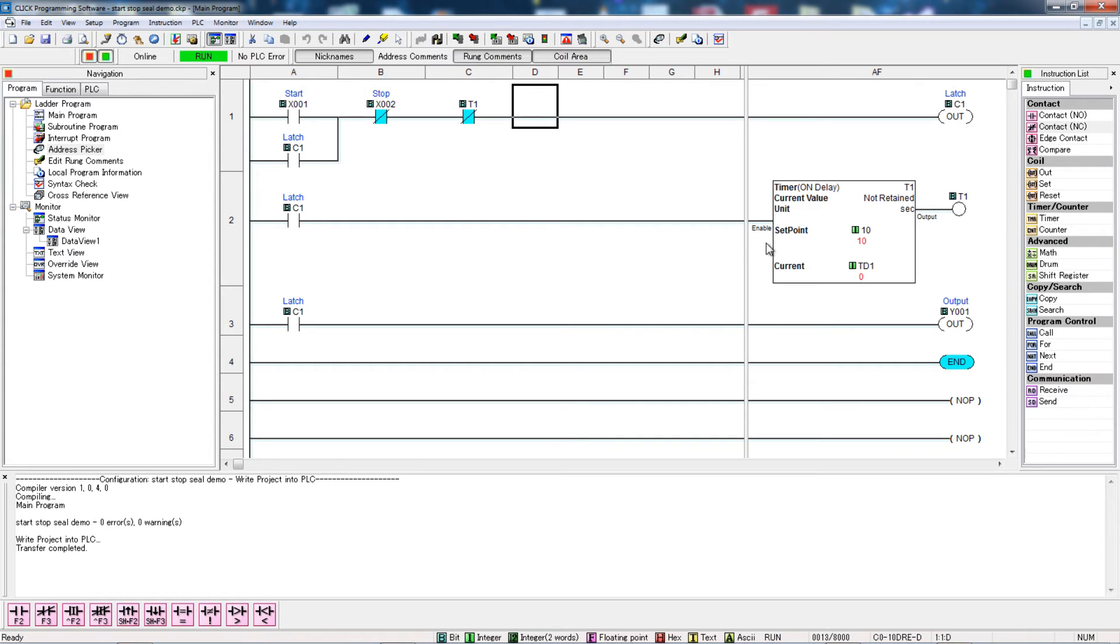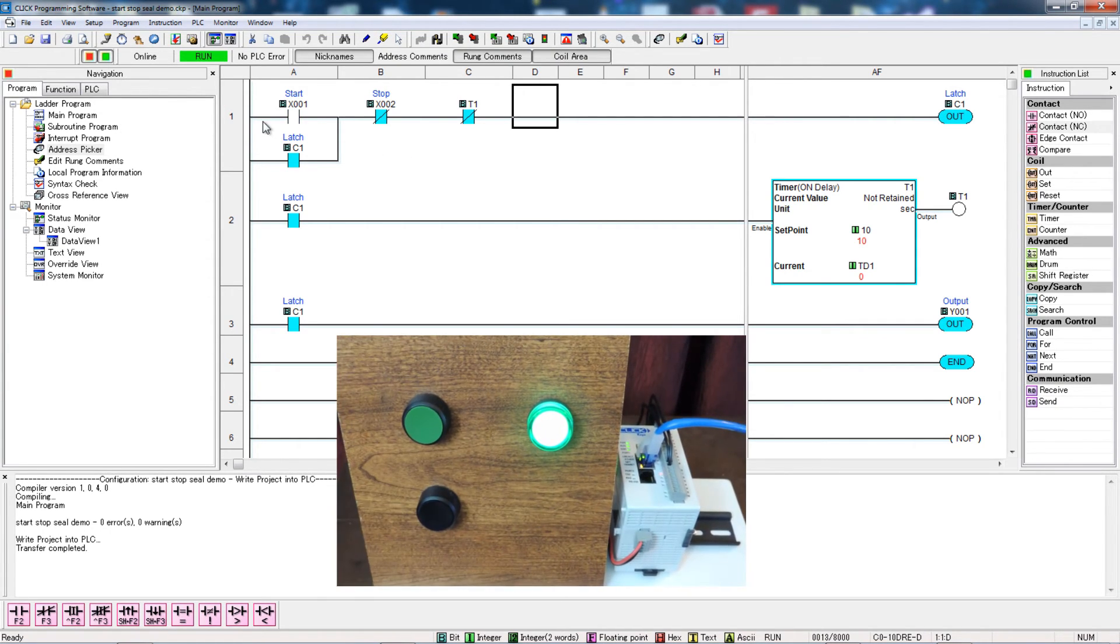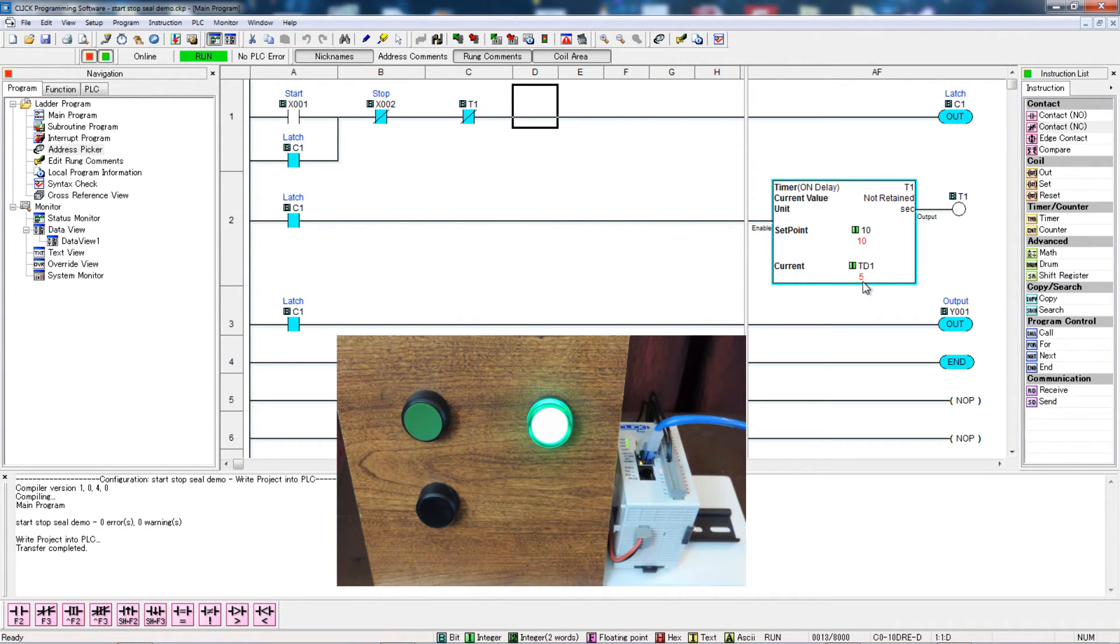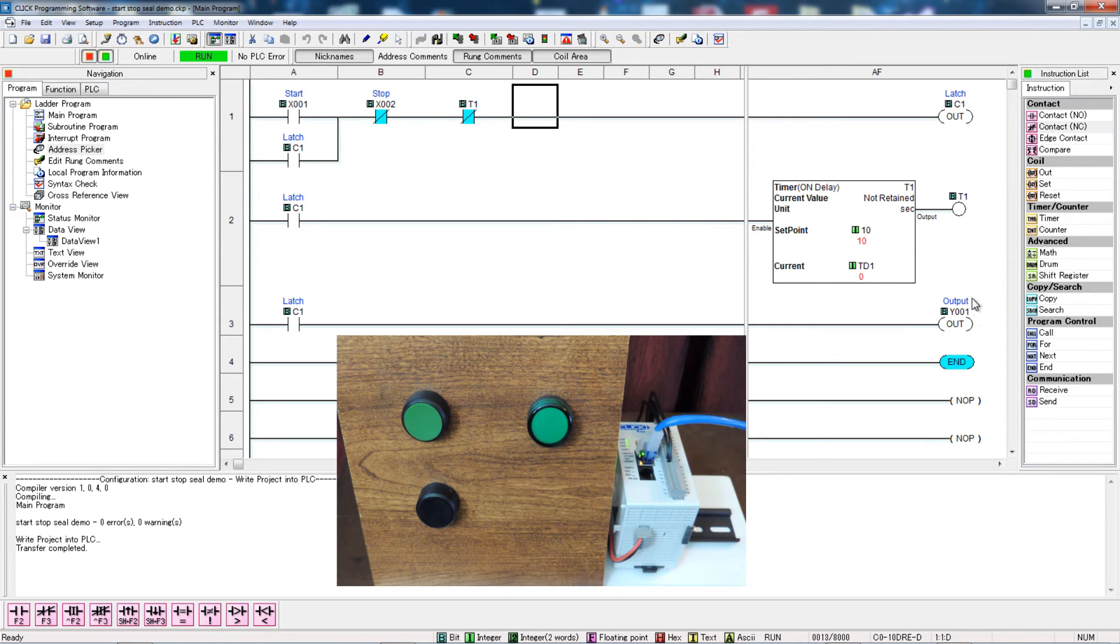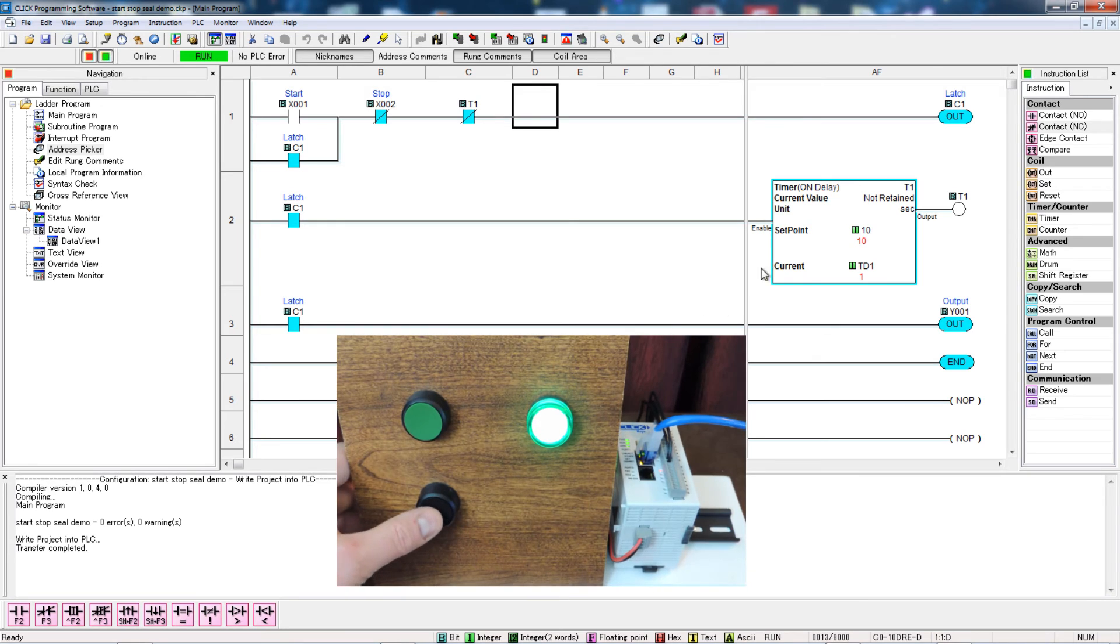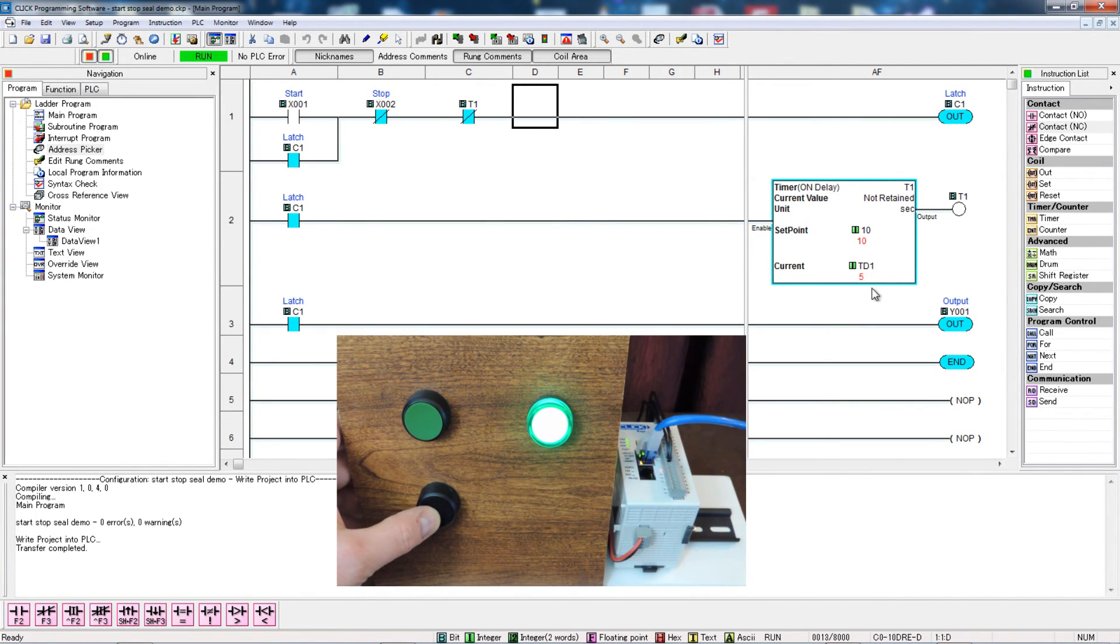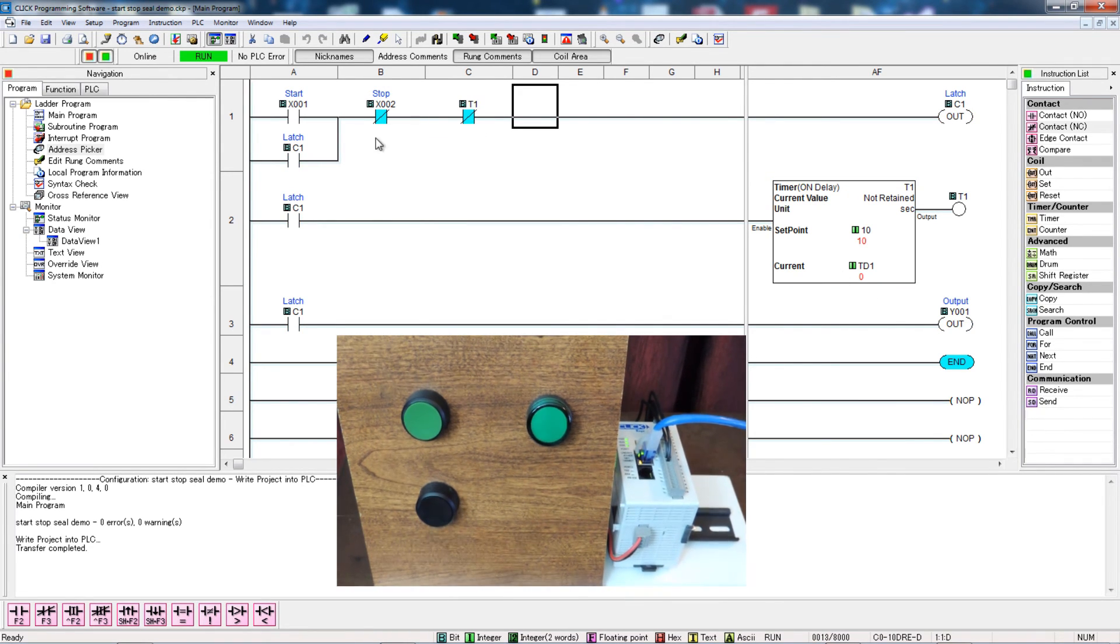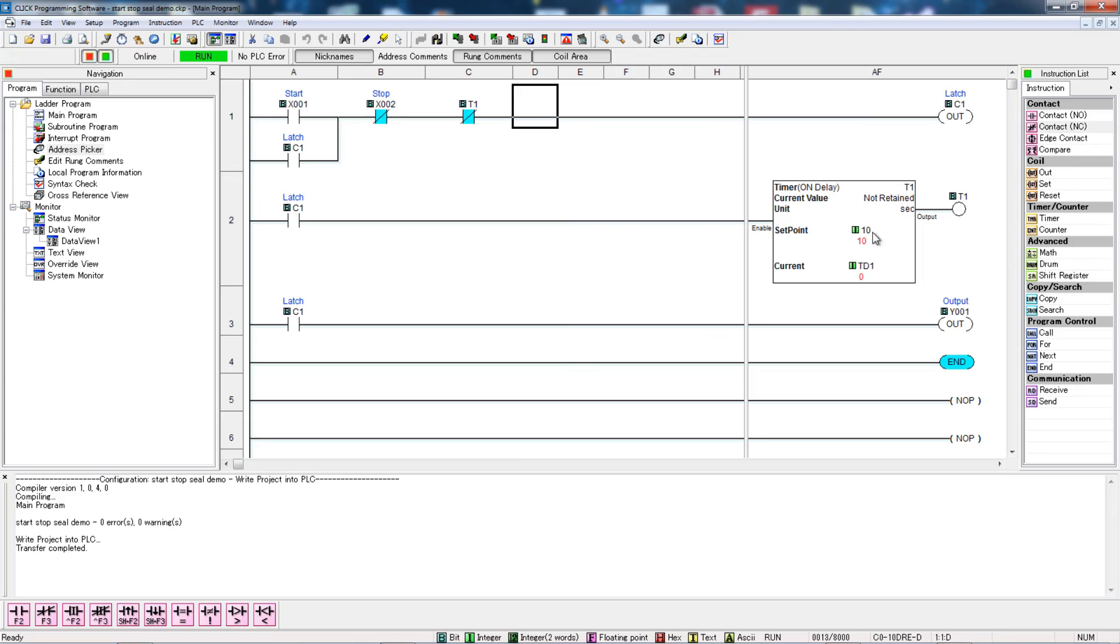There, we can see we're live again. We're in run, and the blue is showing up. I'll go ahead and press the start button momentarily. And there, we passed through on our latch circuit, latches on, and we can see here that our timer is counting down. And we timed out, and the light went off. We'll just do that again. Now, this time, before it gets to 10, I'm going to hit the stop button. So, right about 8 here, stop button. And that caused this to drop out here, causing our output to turn off before it even hit the set point.